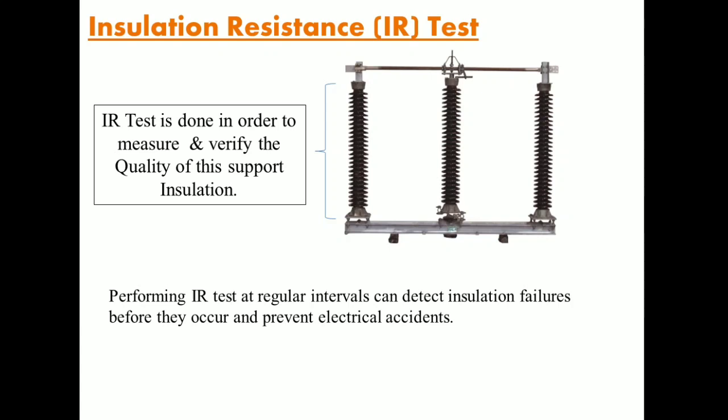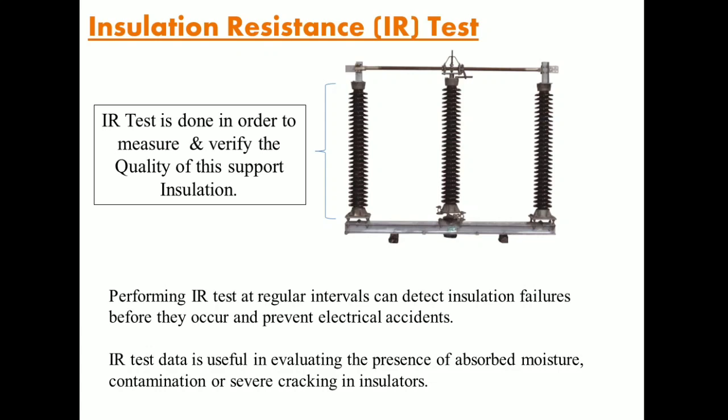Performing IR test at regular intervals can detect the insulation failures before they occur and prevent electrical accidents. IR test data is useful in evaluating the presence of absorbed moisture, contamination of insulation, or severe cracking in the insulators.